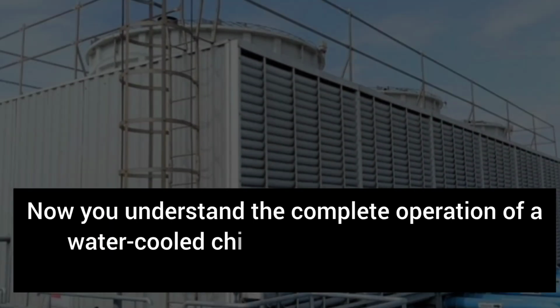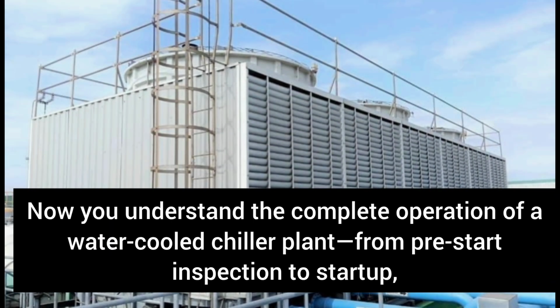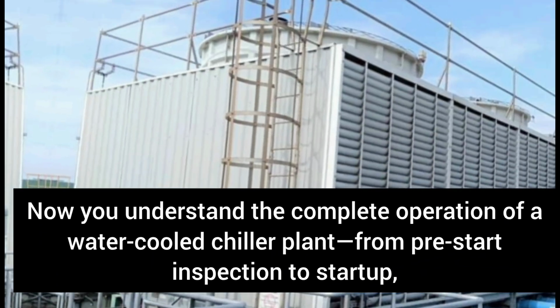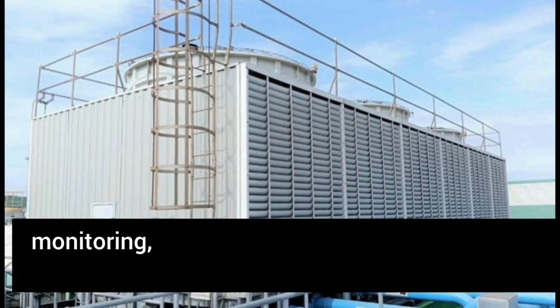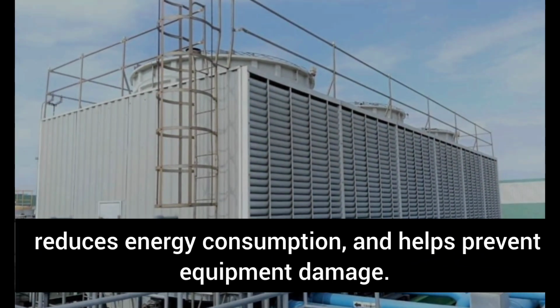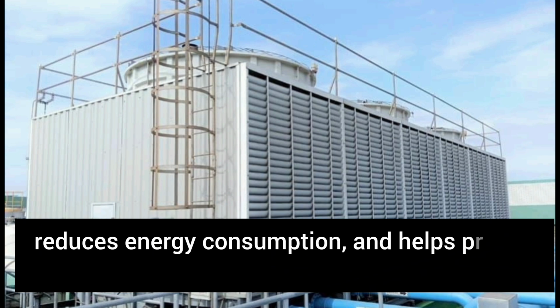Conclusion. Now you understand the complete operation of a water-cooled chiller plant from pre-start inspection to startup, monitoring, and shutdown. Following the correct sequence improves efficiency, reduces energy consumption, and helps prevent equipment damage.